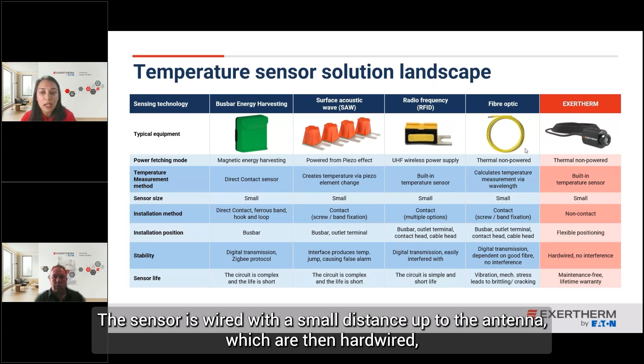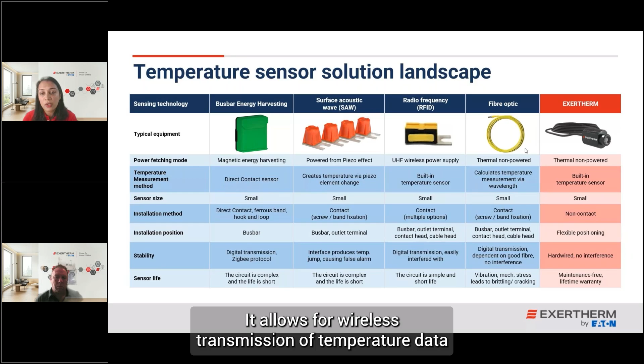Next, we have the RFID sensors. These sensors are small and self-powered by UHF, ultra high frequency, with a built-in temperature sensor, and are directly mounted in contact onto the measurement location. It allows for wireless transmission of temperature data over a short distance, and this can easily be interfered with.